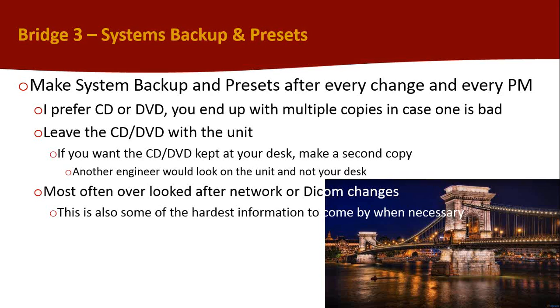So I always suggest to everyone that, each time they work on a machine, each time they make a change, particularly DICOM or network changes, make a backup. If your unit is the kind of unit where maybe it doesn't store the IP address on the disk or it doesn't restore it, the LOGIQ 9s are a great example of that. And also quite often on the Philips 22s and 33s, they will often not restore their IP addresses. Sometimes they do, sometimes they don't, depending on situations. Write the IP address right on the CD or DVD. And it's right there, and it's super easy, and everything goes very well.